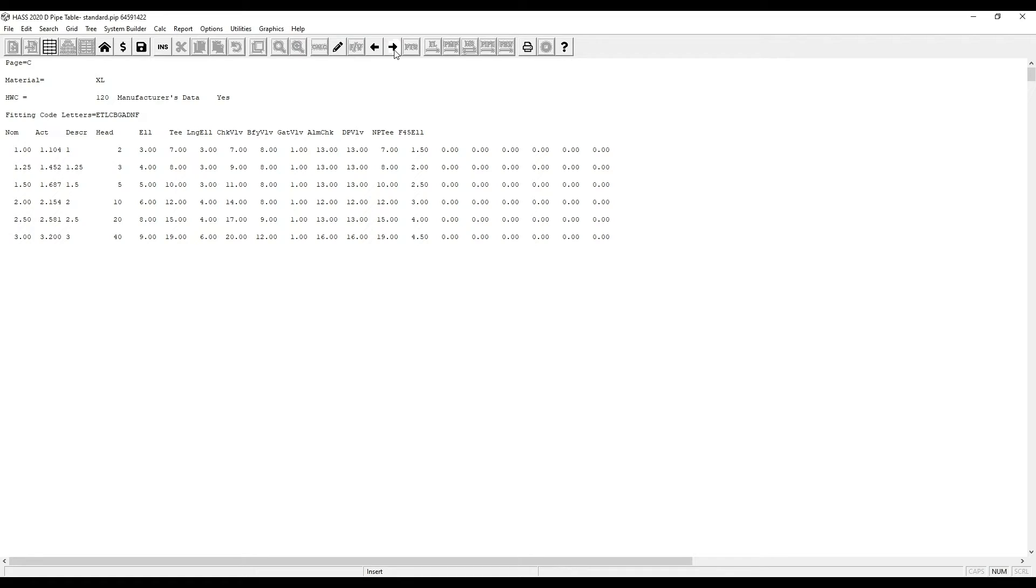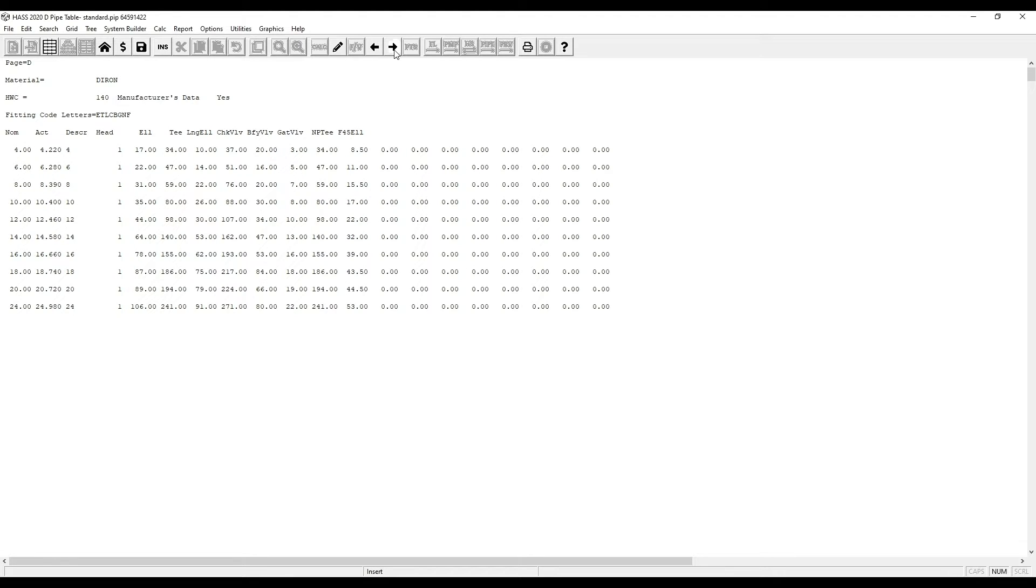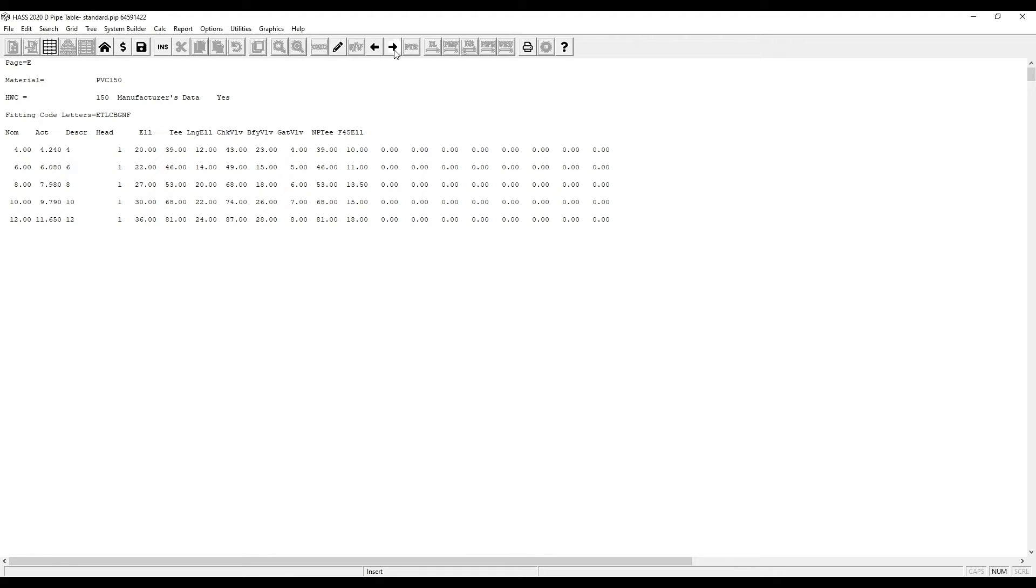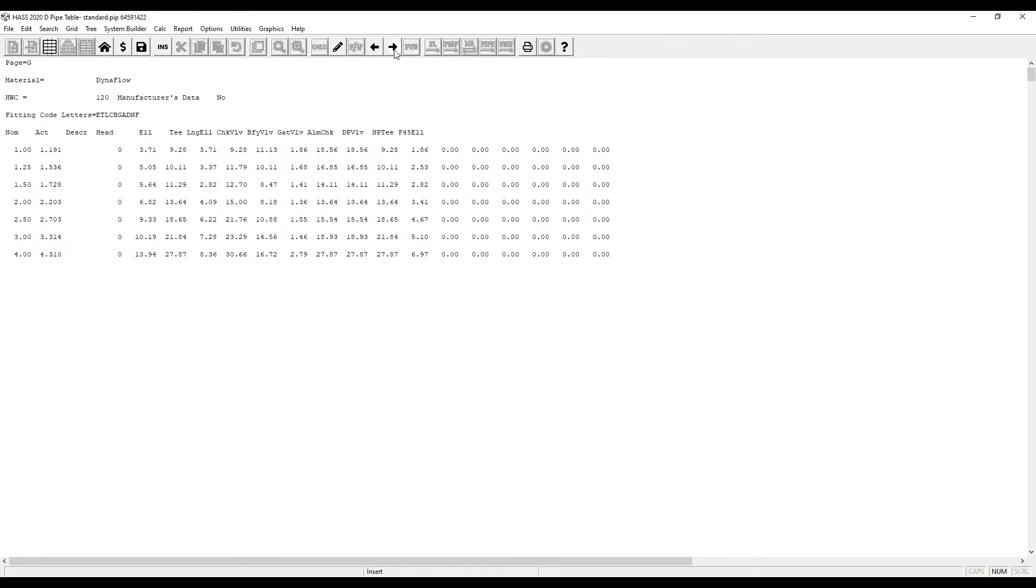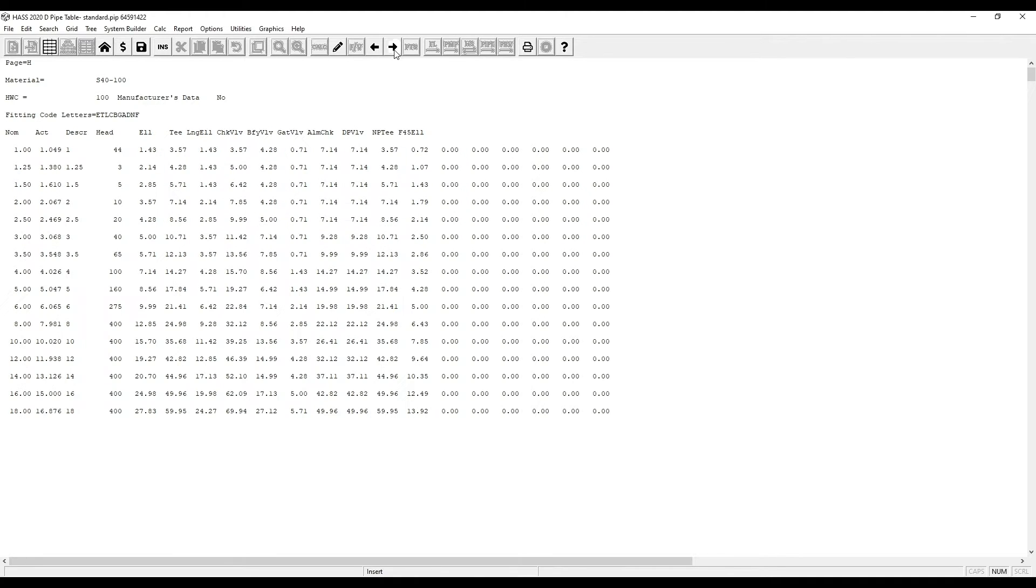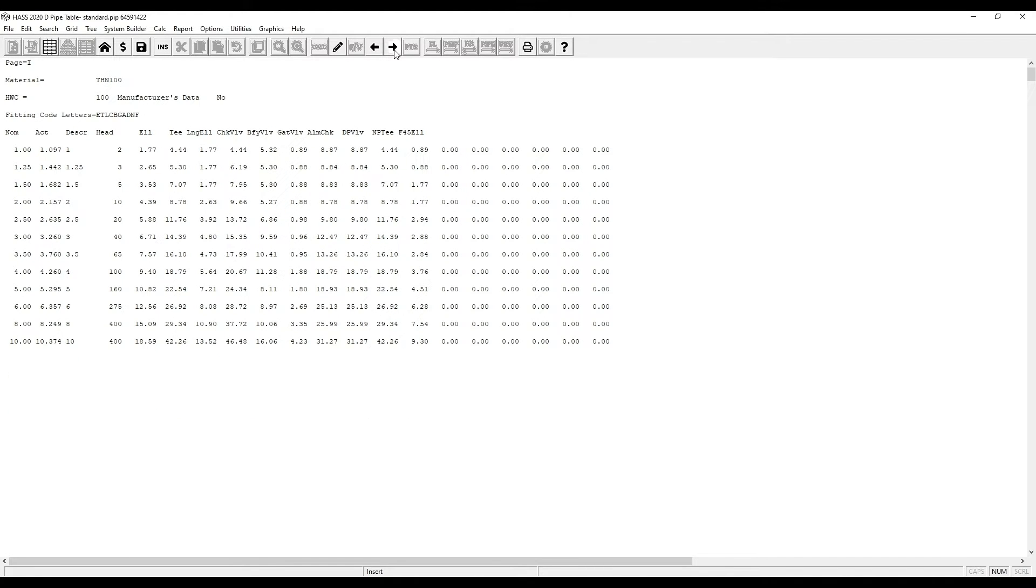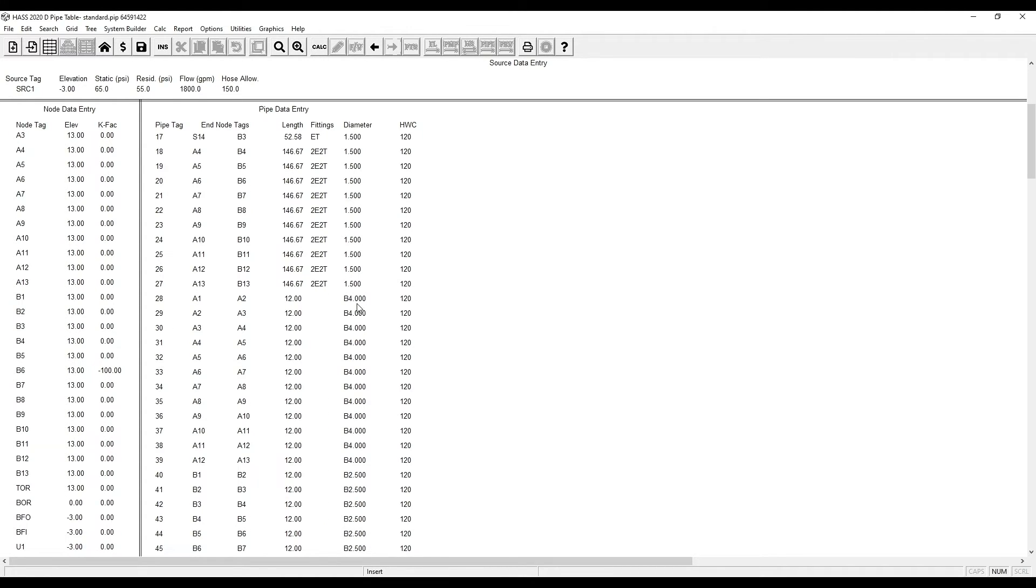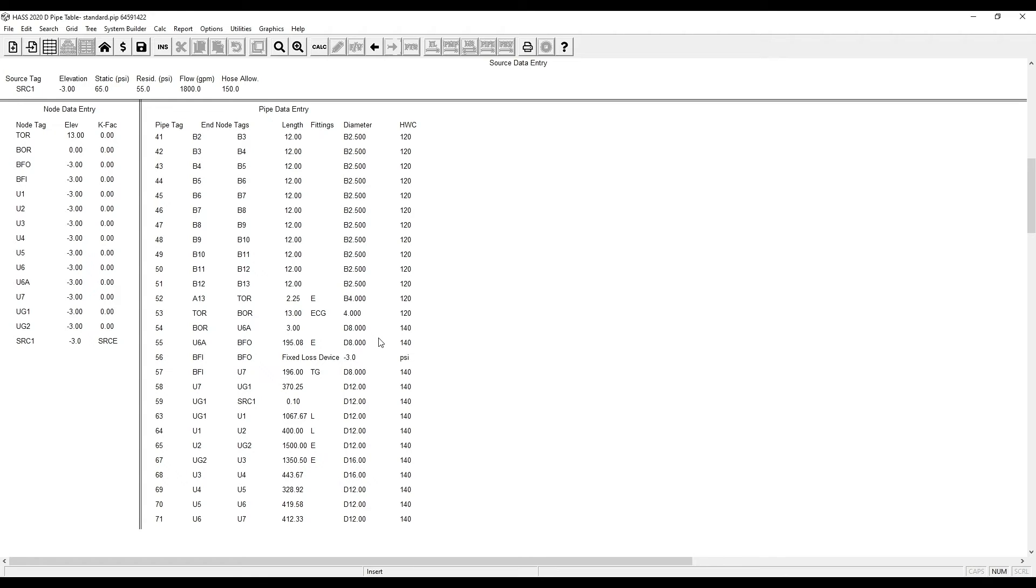We also have ductile iron, PVC, CPVC, along with multiple other default pipe materials. Let HASS know that you would like to use a different material than the default page. Type the pipe page, then the nominal pipe size. Here we have schedule 10, 4 inch. Down here for our underground we have ductile iron 8 inch as well as 12 inch and 16 inch. Verify your pipe table.